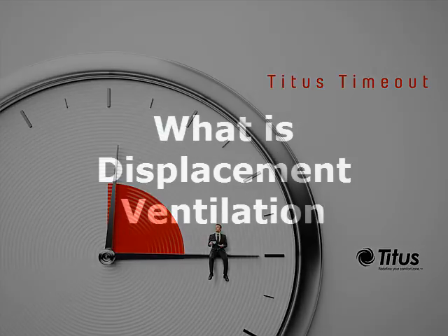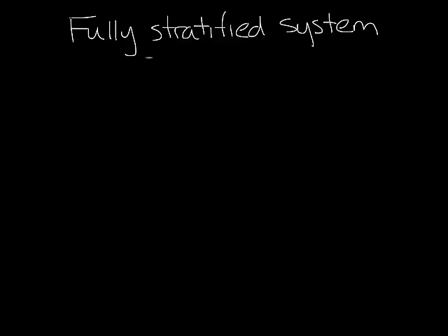I'm Jenny Abney-Civy, and today we're going to discuss displacement ventilation. Like underfloor systems, which I discussed in a previous podcast, displacement ventilation systems came from Europe, where they've been used for quite a while. But in the U.S., they're fairly new to us, but they're gaining popularity, especially in schools. Displacement ventilation systems are defined by ASHRAE as a fully stratified system. This means that there's no mixing in the occupied zone.